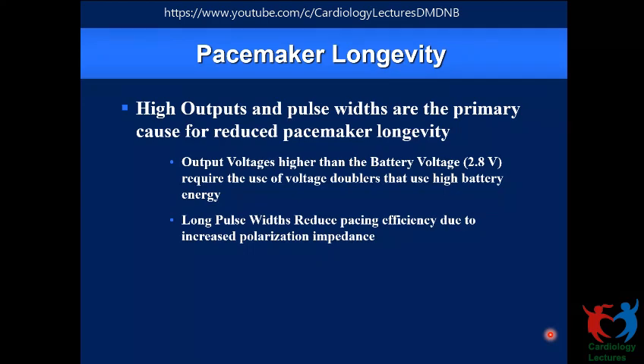But the point comes when you encounter a patient who has a higher threshold. That's where it is worthwhile considering both of these and trying to reach this point and then program an output so that you can conserve the battery as much as possible. Dr. Manish, you want to... Yeah, it's the same thing. The idea about chronaxy and rheobase is to make sure that you conserve as much battery as possible. You use the minimum amount of output for each pulse that you deliver. At the same time, don't compromise on safety. So generally, like what Mr. Govind said, although we get a threshold of 0.7, 0.8, you never see a pacemaker being programmed at 0.7, 0.8 because there might be slight variation in threshold.